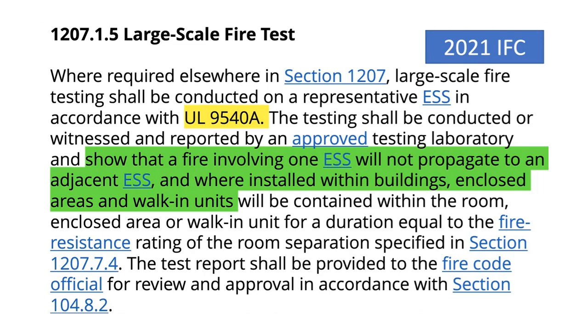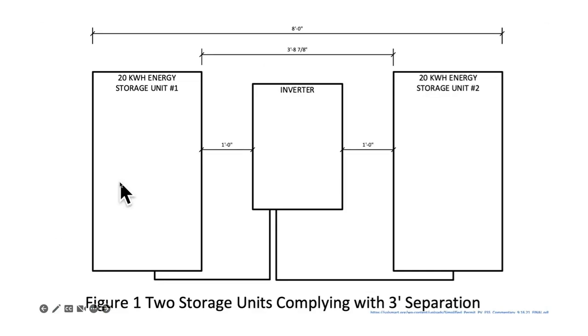And if you look at it and they say, oh, you saw this, then you're just getting liability and more likely to get called into court. If something is listed and it's in the instructions and it's done the 9540A, you could just trust that testing lab that did it. So here's an example of 3 feet apart. If we had an inverter in between that was greater than a foot, and we had a space between the inverter and the energy storage system that was each a foot, according to their instructions, that would be one way of keeping these energy storage systems apart.